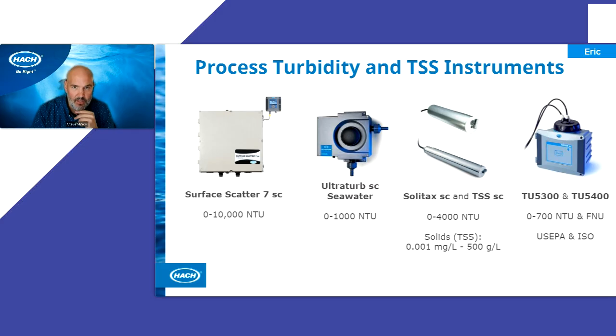But for these optical sensors, they do pretty well within that entire range with a good calibration. And by good calibration, what we're looking at here is essentially, as described with these sensors, you want to take a grab sample and sort of tell the sensor what it's seeing. And once you've established that, and as long as the solids characteristics in the water don't drastically change, if your process shifts, you may want to do another grab sample in comparison. I'd recommend for stable systems, still checking that probably monthly. Maybe a couple times a month wouldn't hurt.